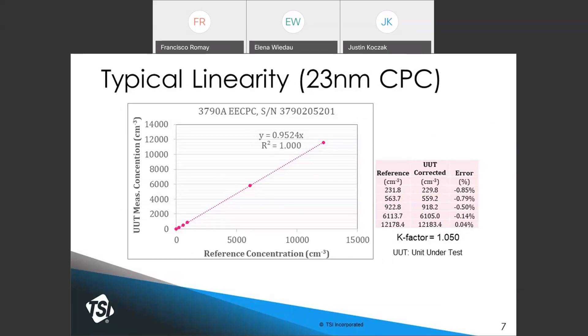A typical linearity curve for a 23-nanometer CPC — in this case the TSI 3790A — shows that for current regulations, the typical concentration range is up to 10,000 particles per cc. There is a limit on the coincidence factor that can be applied, which must be below 10%, creating an upper range limit. This instrument shows very linear performance with an R-squared of nearly 1, a slope of 0.954, and a reciprocal K factor of 1.05.